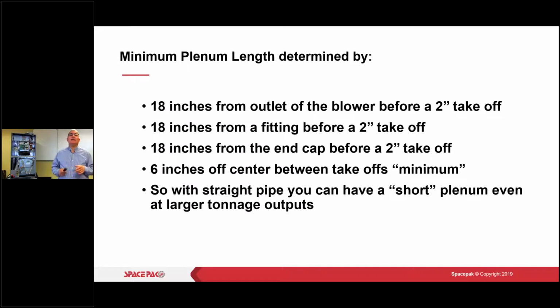Here's where we see issues out in the field. All right, we have 18 inches from the outlet of the blower before a 2-inch takeoff. Sometimes we'll see systems installed where that is too close. That causes a problem. We want to stay 18 inches from a fitting before a 2-inch takeoff. I'm sorry, I misspoke. So 18 inches from the fitting before the 2-inch takeoff, 18 inches from the end cap before a 2-inch takeoff.